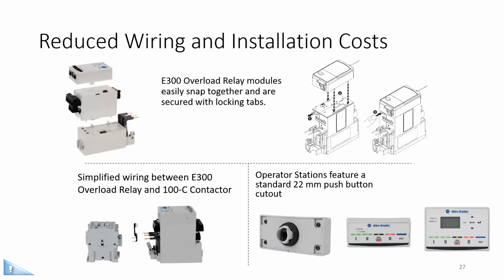The E300 was designed to be modular, so that reduces the number of SKUs, makes it easy to install, and reduces wiring needed for 3-component combination starters. The 3 main modules are easy to install and secure. There are just little tabs that you push in and lock down. You put any communication module on the top, and all modules have removable terminal blocks for control wiring. So you can remove the terminal blocks, replace the module should it go bad, and then snap them back in.